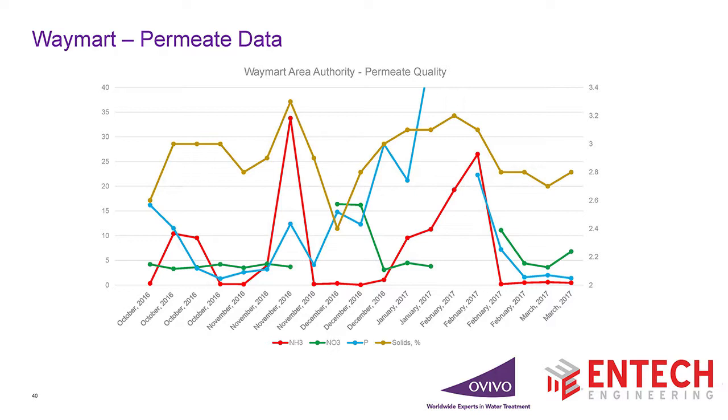And again, it's not just the membrane. You have to have the digestion working correctly also. So again, it shows with operator attention. These are good operators, but again, they're learning a process. But with operator attention, paying attention to the details, you can get excellent side stream quality.